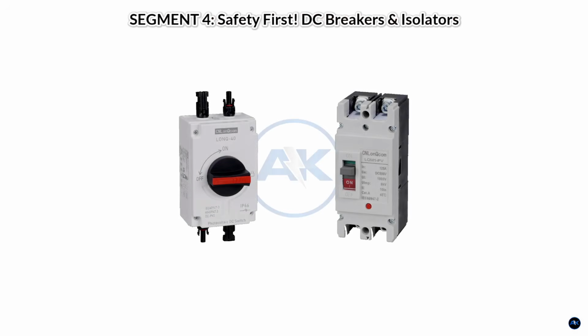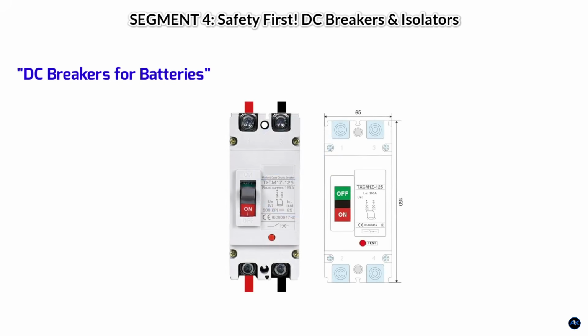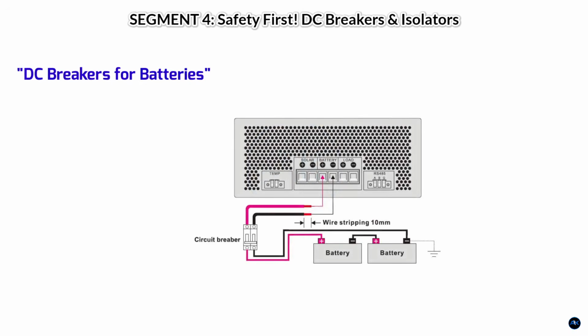Segment 4. Safety first. DC breakers and isolators. Safety is paramount in any electrical installation and solar is no exception. DC breakers and isolators are your essential guardians. DC breakers for batteries. These are vital for protecting your battery bank from overcurrents and short circuits. Placement: usually located immediately after the battery bank, before the inverter's battery input.